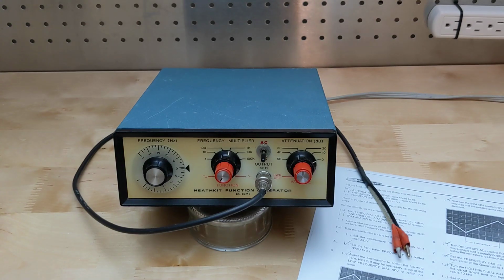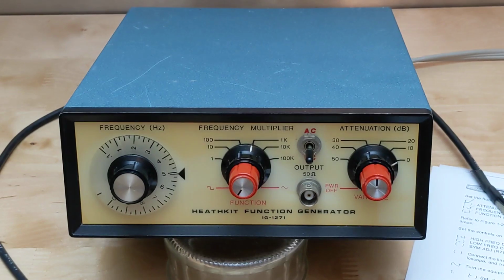The unit generates sine, square, and triangle waveforms from 0.1 Hz to 1 MHz in six ranges. It features a 50 ohm output impedance, and the output is variable up to 10 volts peak to peak into a 50 ohm load or greater. A calibrated attenuator switch goes from 0 to 50 dB in 10 dB steps, as well as a variable attenuator control with a 20 dB range. It can be wired for 120 or 240 volts AC, 50 or 60 Hz, and weighs about 4.2 pounds or 1.9 kilograms. The three-position function switch selects the output waveform, square, sine, or triangle.